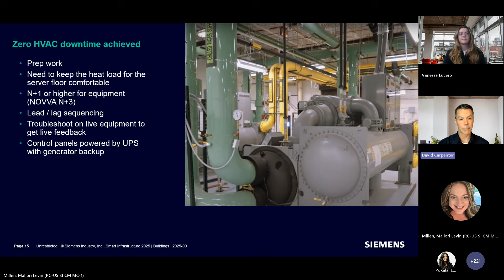One of the things that is very important in a critical environment, especially a data center, is that all of the control panels are powered by the building's UPSs and generator backups. That may seem like a no-brainer, but that's not always the case from an older building. And so it is something that we want to make sure we never see a controller having to reboot because of the downtime in between a generator kicking on. That would create false alarms that came about just from poor power quality. So that is an important aspect of maintaining a healthy building, is having healthy power to every one of the pieces of equipment.